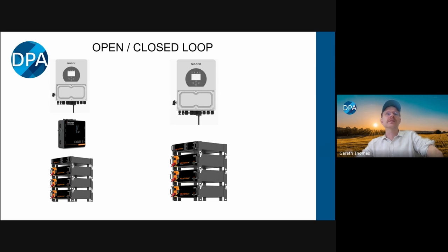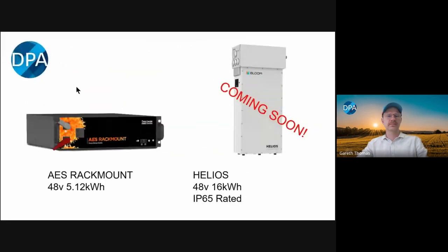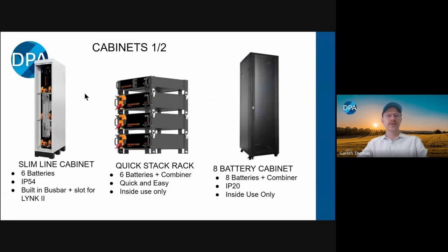So there's a question from Pedro that I hadn't noticed. Where would you locate the combiner in the rack? So what Pedro is asking is, let's go back. If we're using a quick stack rack, you've got the combiner box here. Because the quick stack racks are only 6 batteries high, you can put it at the top or the bottom or the middle. You can do whatever you like, and the cables will reach all of them. If you were putting it in the 8 battery cabinet, you'd put it in the middle, so you've got enough cable length to get to the bottom and the top batteries. If you put it at the top, it wouldn't reach all the way down to the bottom. But otherwise, when you're just doing the quick stack rack, you can put them wherever you like, really.